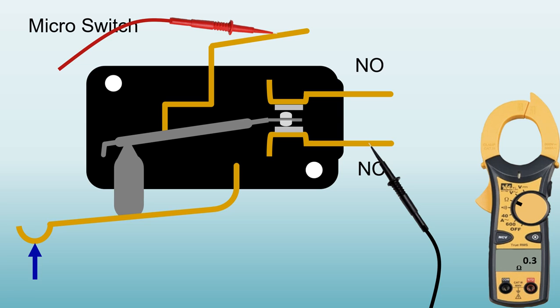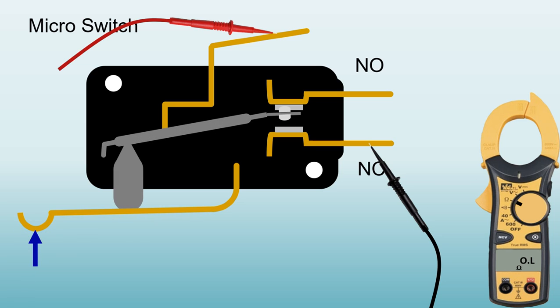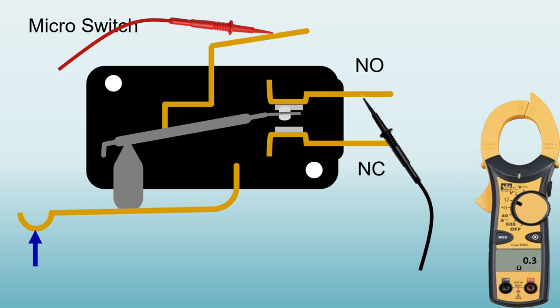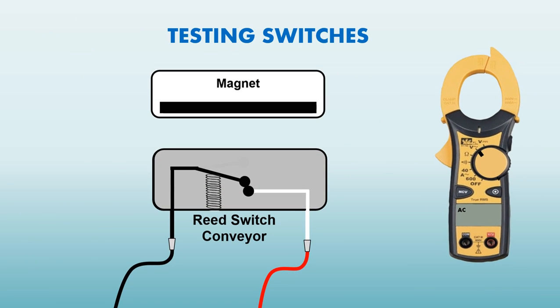Let's run a continuity test on a micro switch. Again, the test runs in the same manner. We would take one meter lead to the incoming source and one meter lead out to the normally closed. In this case, it's showing that the switch is a full contact and that the switch is working. If we move the switch to the normally open side, we take our meter lead, we move to the normally open, and we verify that it also has contact and that the switch is working correctly.